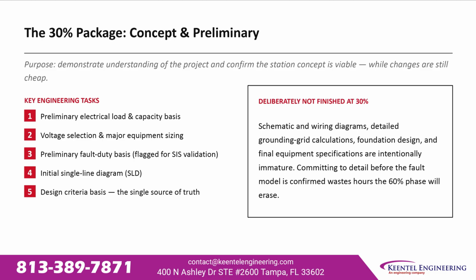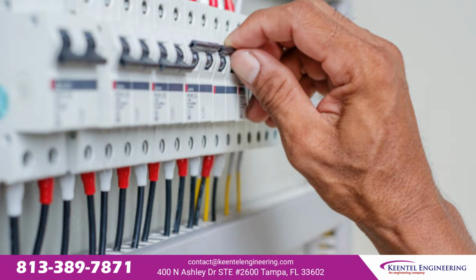What is deliberately not finished at 30% matters equally. Schematic and wiring diagrams, detailed grounding grid calculations, foundation design, and final equipment specifications are intentionally immature. Committing to that detail before the fault model is confirmed wastes hours the 60% phase will erase.